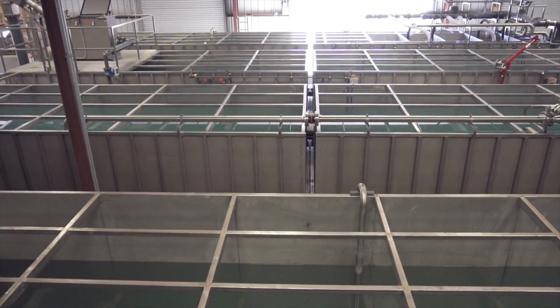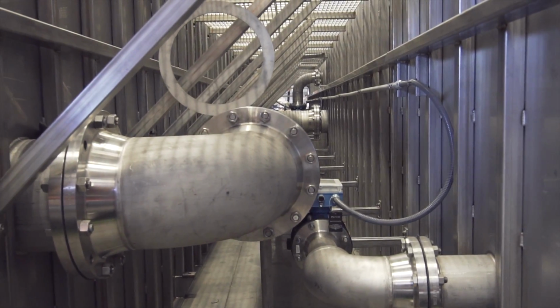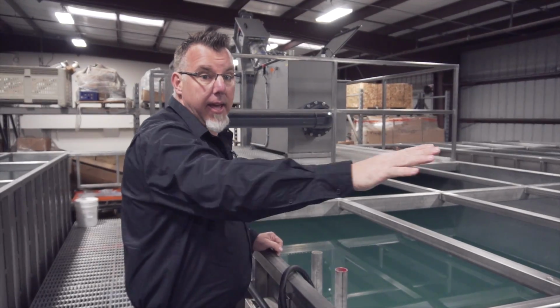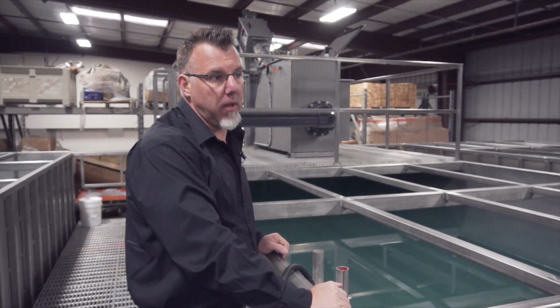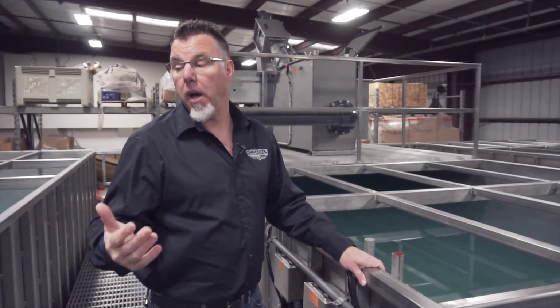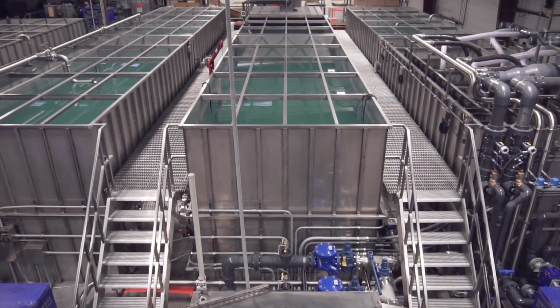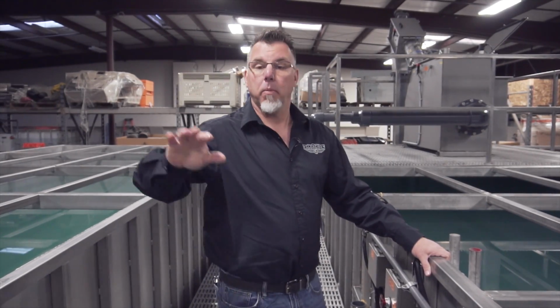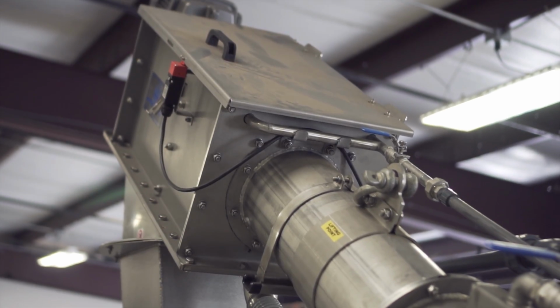Once the daily flow reaches 40,000 gallons per day or above, the client's able to remove a blind flange and change valving that is already installed in the project and increase the capacity up to 250,000 gallons per day average daily flow. Phase 2 will increase this flow range to 350,000 to 500,000 gallons per day by the addition of 2 more aeration anoxic trains. Phase 3 will be the addition of another anoxic train and redundant influent screening.